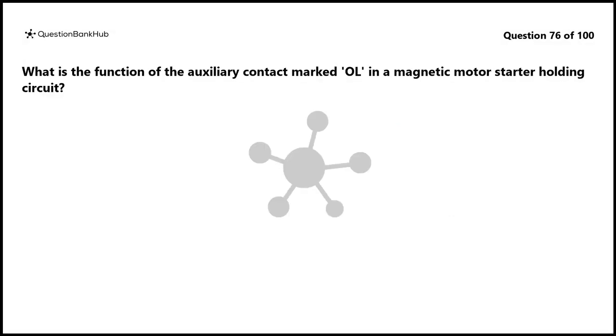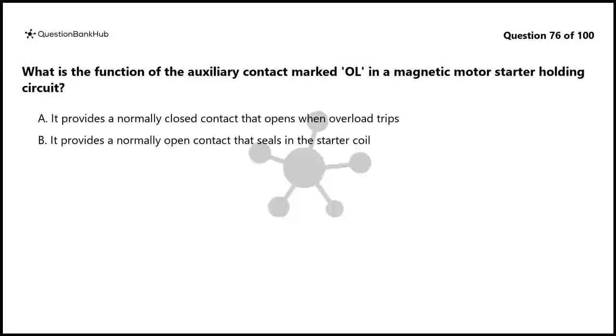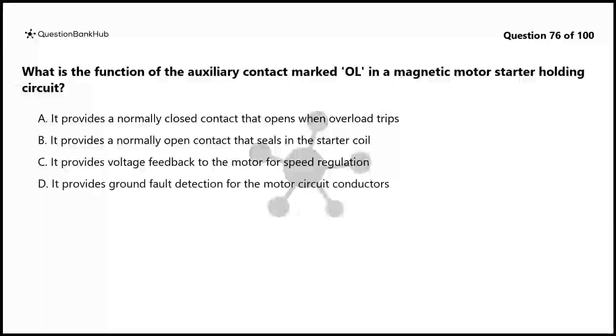Question 76. What is the function of the auxiliary contact marked OL in a magnetic motor starter holding circuit? A. It provides a normally closed contact that opens when overload trips. B. It provides a normally open contact that seals in the starter coil. C. It provides voltage feedback to the motor for speed regulation. D. It provides ground fault detection for the motor circuit conductors.